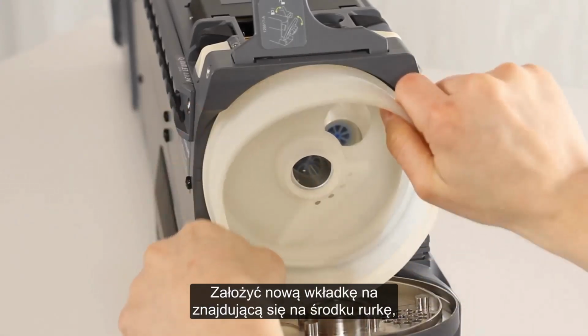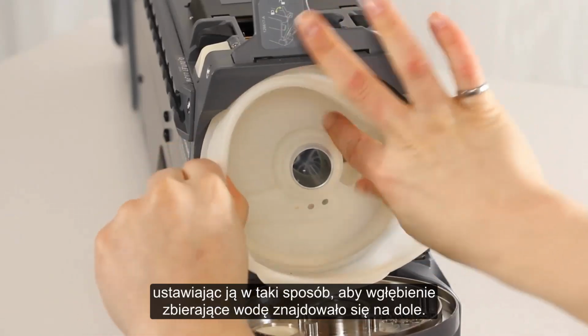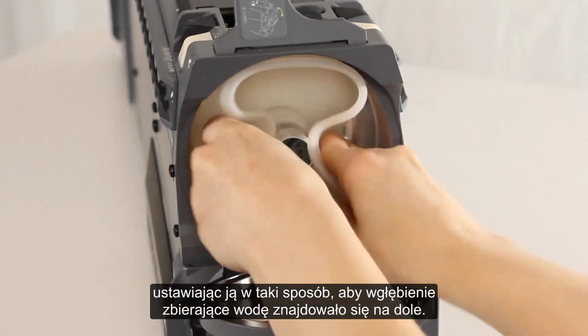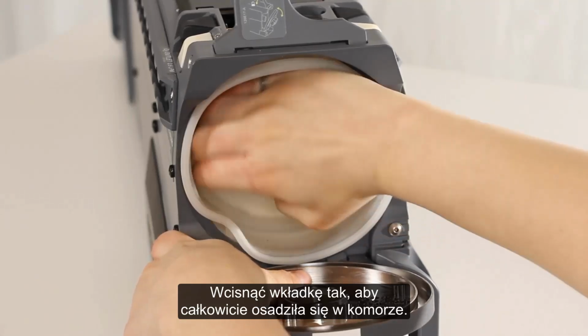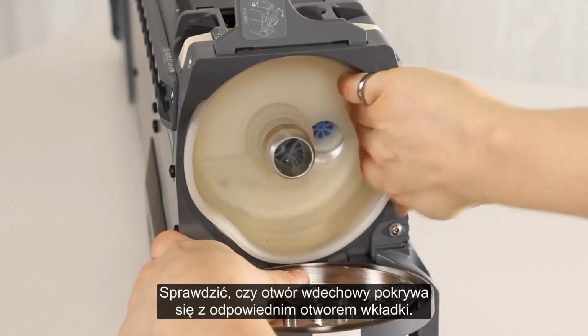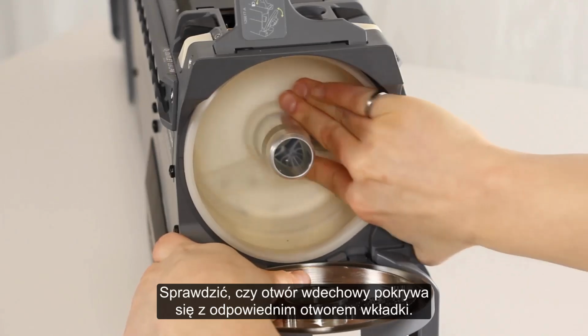Place the new liner on the middle tube, orienting it such that the water collecting cavity is at the bottom. Push the liner back until it is fully seated. Ensure that the inspiratory hole matches the corresponding liner hole.